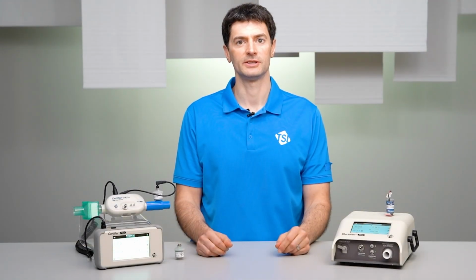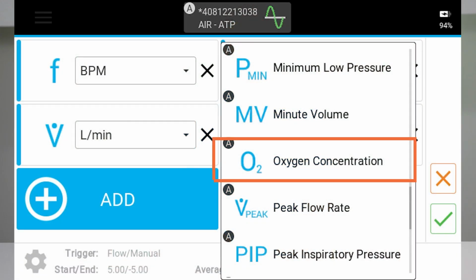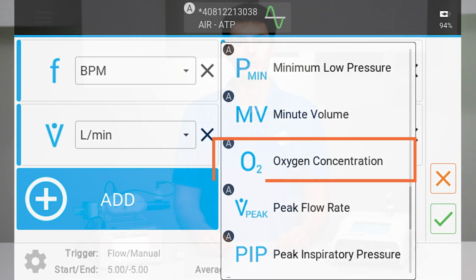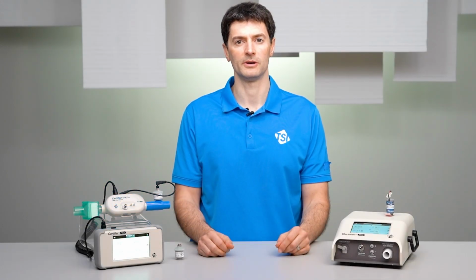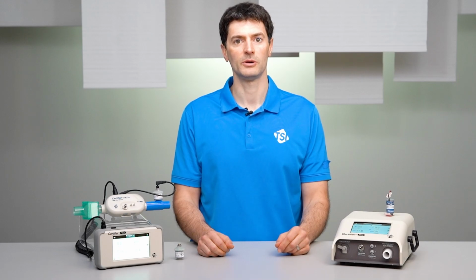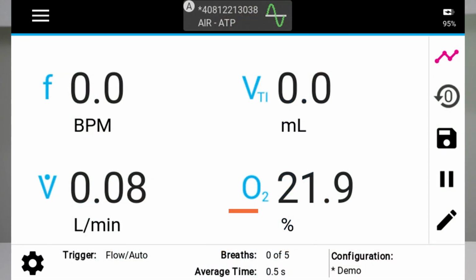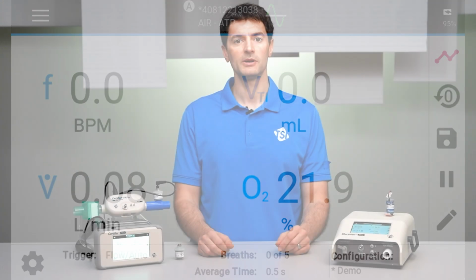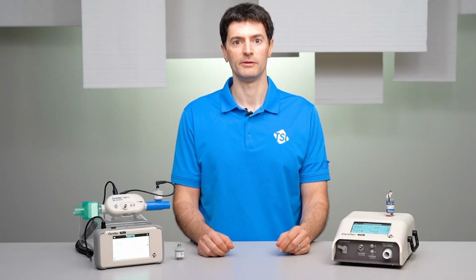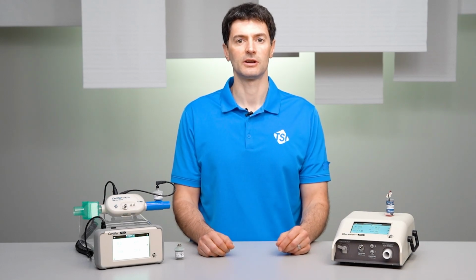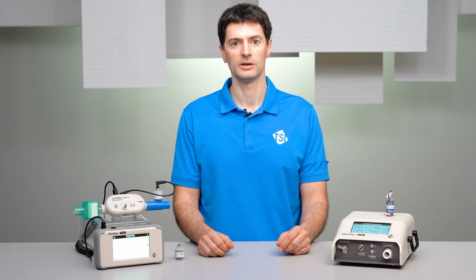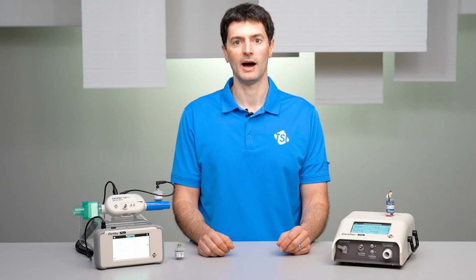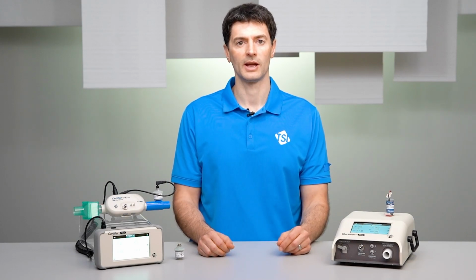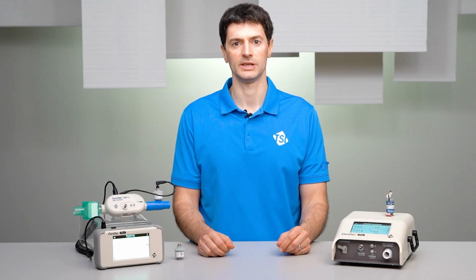When an oxygen sensor is connected, select the oxygen concentration measurement from the Certifier's touchscreen, just like you would any other measurement parameter. In addition to viewing real-time readings, measurements from the oxygen sensor can also be graphed, and its measurement data can be logged. It's recommended that you calibrate the oxygen sensor before taking measurements to ensure the most accurate readings. The oxygen sensor can be calibrated with a 1-point air-only calibration or a 2-point air and oxygen calibration. A 2-point calibration will provide the highest level of accuracy.